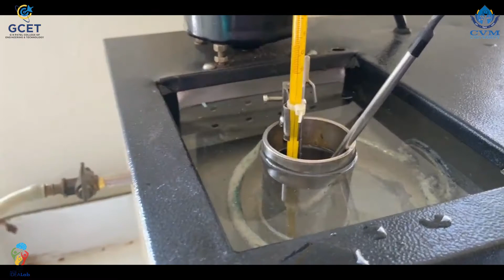This is the setup that we have for calibration of our RTD. Here you can see we have one heating unit inside, which right now is filled with water, and in the inner chamber we have oil that is filled.